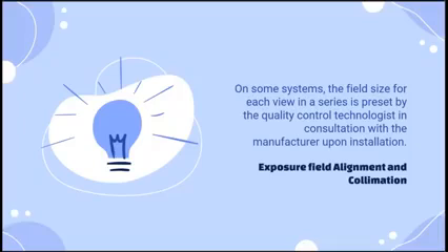When we x-ray the patient, the field size should be appropriate for the size of the body part. If you compare the hand of an adult and a child, of course the adult's is bigger. If the preset installed by the QC technologist is for an adult, that means for the child the field size is too large, which will increase the dose, increase scatter radiation, and ultimately increase the patient dose of the child.